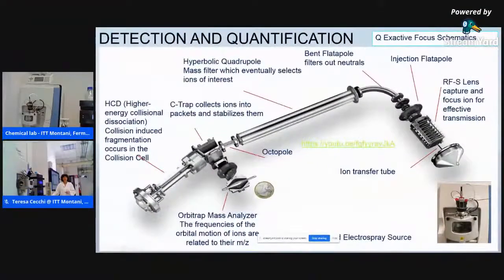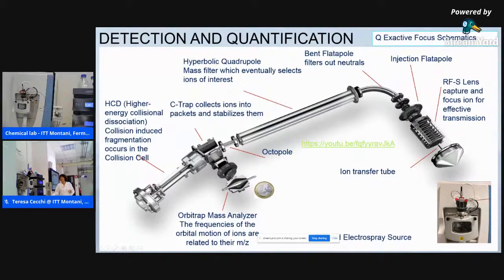After the sweep cone, we find S lenses that capture and focus ions for effective transmission into the mass spectrometer. And then we have a bent flatapole which filters out neutral species, because neutrals, if they have entered the system, would follow a linear path. They would not bend. So this bent flatapole filters out neutrals. And then we have a mass filter that is a quadrupole that only selects ions of interest. We will see it later.